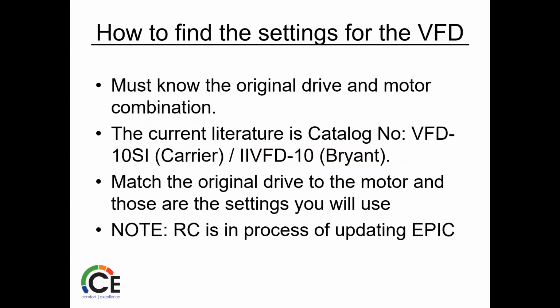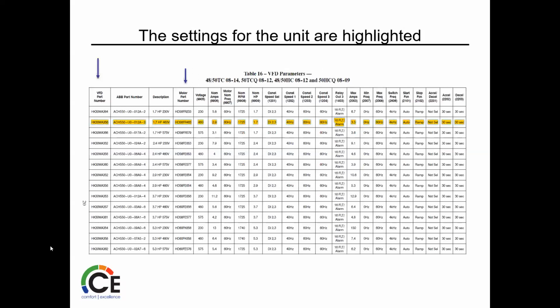If you're calling for parameters and you're calling for help to set up, test question by the way, I need to know the VFD part number, so the drive number, and we need to know the part number for the motor. Now these changed a little bit, but a lot of the books that I have the old number and the new number, so that's not a big deal. So we need the VFD part number, which is that HK30WA, whatever it ends up being. And then you've got to know the motor part number, so we know if it's an HD 56 FE or FR or whatever. As long as we have that, then we can start to go across the line here and check parameters.